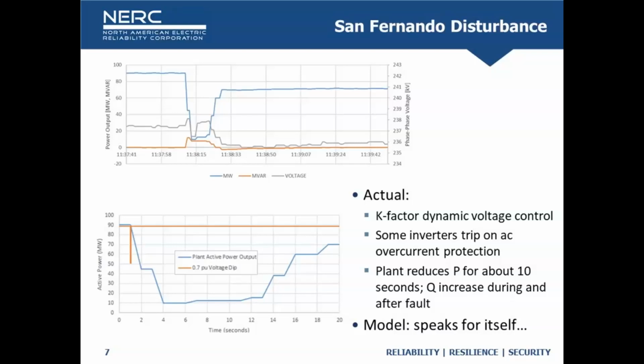But in reality, the resource is doing something very different. And again, it's likely attributed to some interaction of the inverter controls, plant level controls, et cetera. So we did study this for a 0.3 per unit dip, a 0.7 per unit dip, a 0.8 per unit dip. All of the simulation results looked identical to the orange one you can see there. So we sort of were able to say, we don't have the actual data of what the facility saw at the POI.